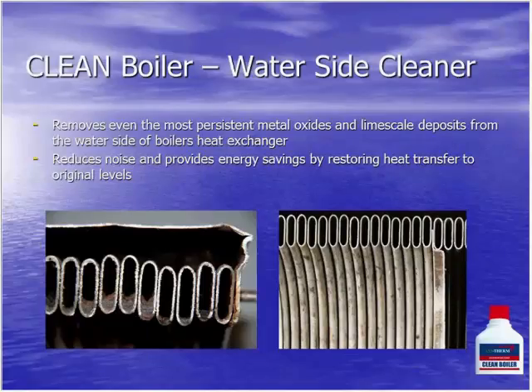Once he had filled it back up and fired it back up, it got back up to 80% firing rate, and it got him through this last week. Then he returned in the spring to properly finish and thoroughly clean that heat exchanger and clean the distribution system as well. So it got him through the first winter and cleaned what the other ones he had tried couldn't. But it's designed for the heat exchanger and near boiler piping only, not designed to clean the entire distribution system.